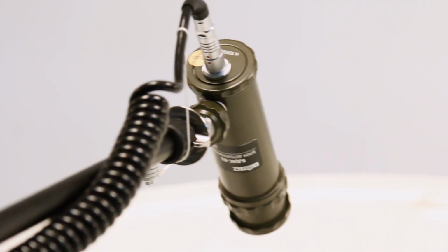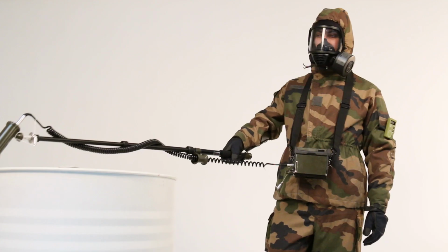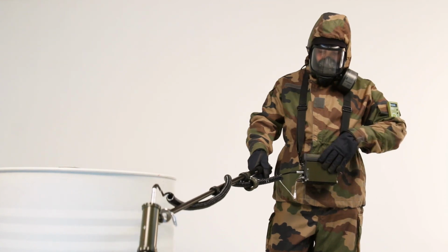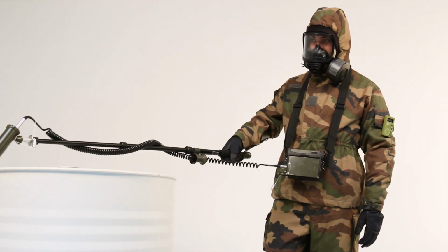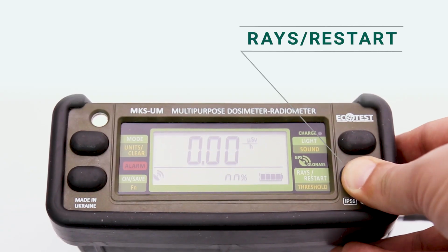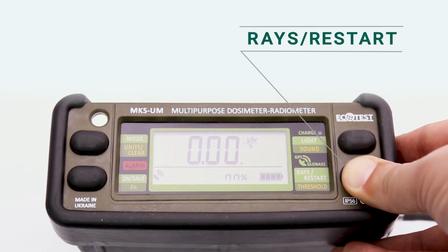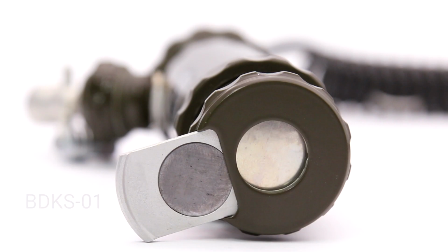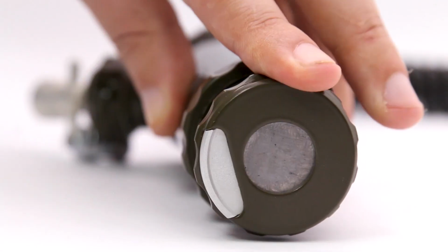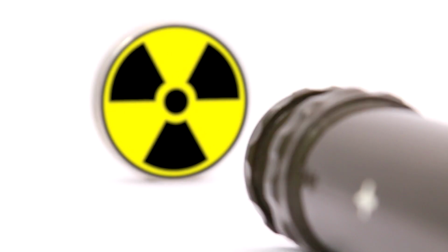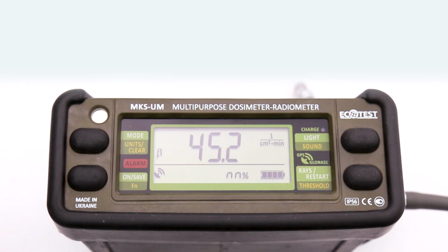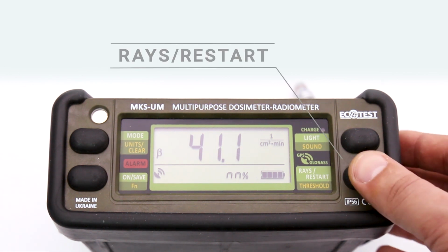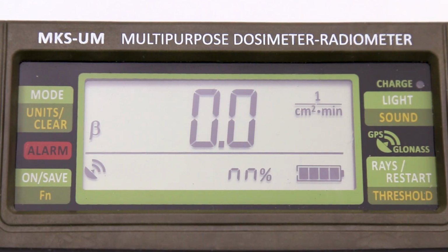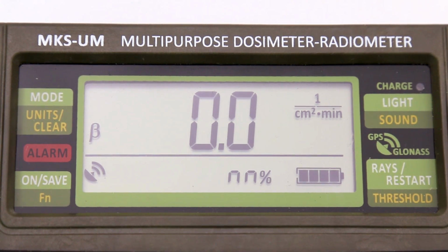Before measuring the beta radiation parameters by the BDKS-01 unit, it is necessary to measure and record the gamma radiation value. This value will be further automatically considered. Select the mode of displaying the results of beta radiation. Place the BDKS-01 unit with the beta detector window kept closed in parallel and at a minimum distance from the inspection surface. Press Rays/Restart to restart the measurement process. Wait for the gamma radiation measurement results with a sufficient statistical error.